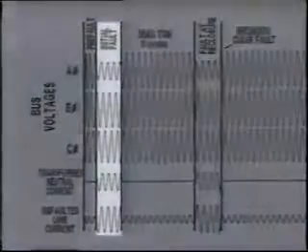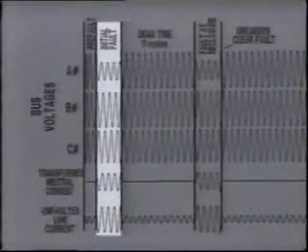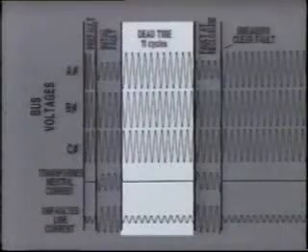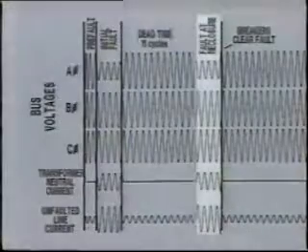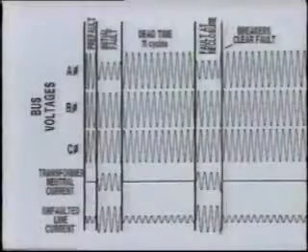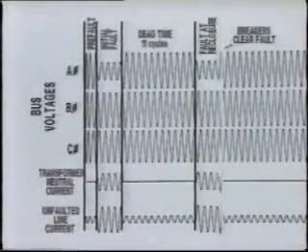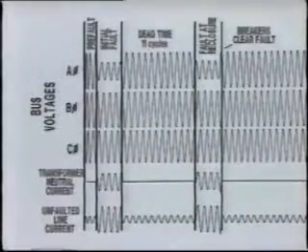We can also tell that the fault duration is 4 cycles. And the line dead time is 11 cycles. At this point, the breakers on the faulted line reclosed, but the fault was still there. So the breakers immediately tripped out again and locked out.